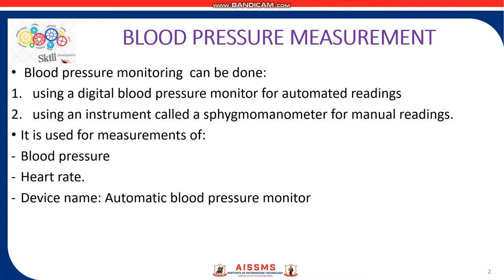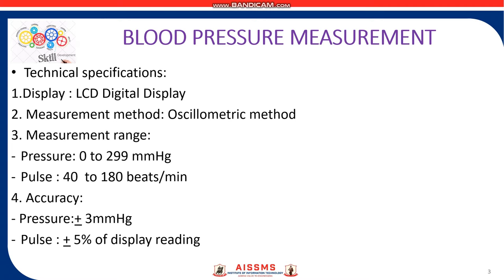Blood pressure monitoring can be done either by using an automatic digital blood pressure monitor or by using an instrument called a sphygmomanometer, which gives manual readings. The device also measures heart rate. The technical specifications of the device include an LCD digital display. The oscillometric method is used for measurement. The pressure measurement range is from 0 to 299 mmHg and for pulse it is 40 to 180 beats per minute.